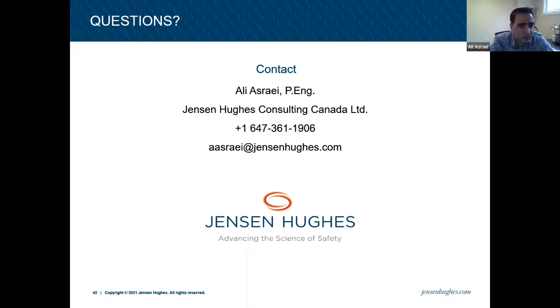So how does the testing you explained translate into the bottom line requirements of OBC Division B 3.2.6.22 for 1% of smoke contamination in 2 hours? I think if you follow the measures, those measures automatically take that into consideration. That is provided by the OBC, and when you go through the SB4 requirements, it's explained there. The requirements for the fan size and the vent size all take that 1% of smoke contamination into consideration. Nobody provides a design saying they did the calculation for 1% smoke contamination in 2 hours. As long as you follow a measure, that's acceptable because those measures are based on this requirement.